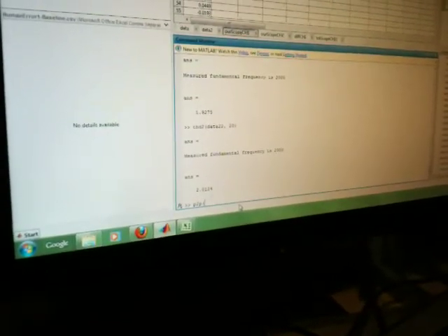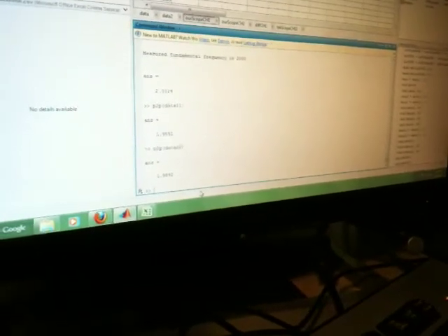The last thing that we need to check is that the peak-to-peak values are not more than 5% different. So I have a nice little peak-to-peak script that I'm going to run here on the first data set. And our peak-to-peak value is 2 volts. Is that what it's supposed to be? Mm-hmm. Okay, 2 volts. Shows you what I know. And the peak-to-peak value of our second, wow, they're exactly the same. So we measured the exact same peak-to-peak value on both data sets. So the peak-to-peak values are obviously within 5% of each other. That should fulfill all the requirements for this test. So I will post both of those scripts on the website as proof, along with the CSVs that we captured.